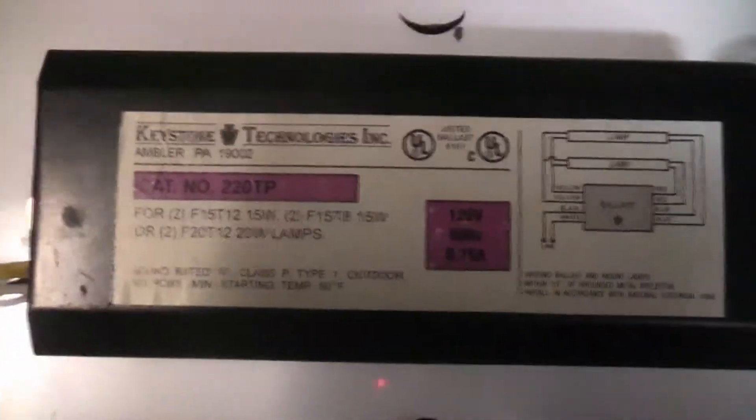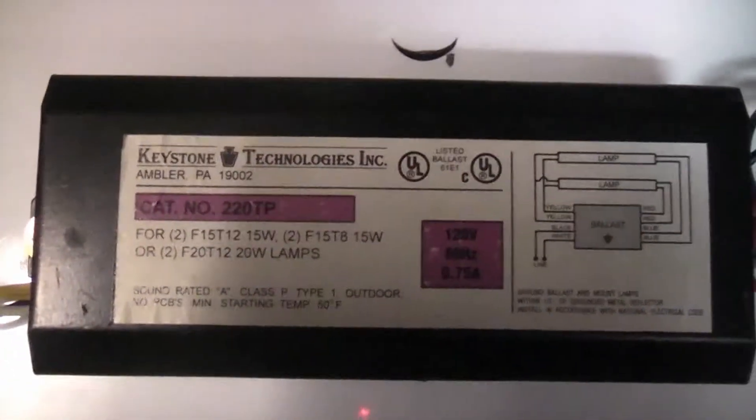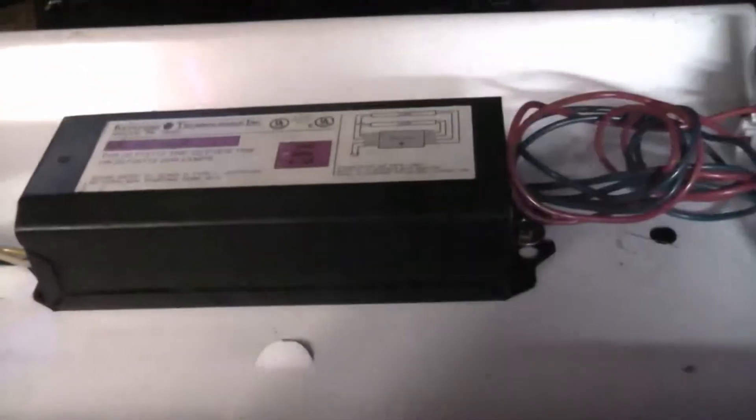Here's the ballast that's in here. I'm imagining this is from the 90s or early 2000s. And we're going to just go ahead and remove that. It is warm, not hot. The new ballast is longer, but most fixtures have fittings. This is a low power factor ballast. But if you look, I can mount it there. And then they normally have areas to mount a high power factor ballast. And that is it. Most fixtures have provisions for both.